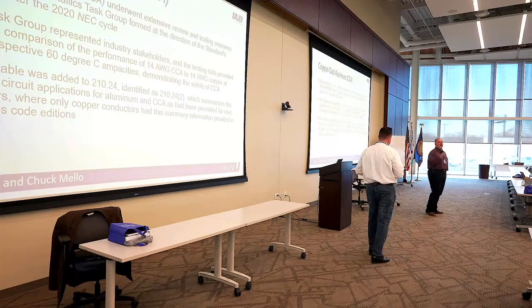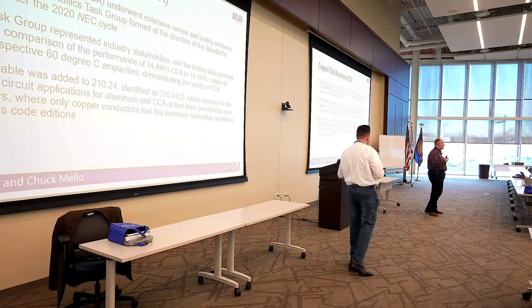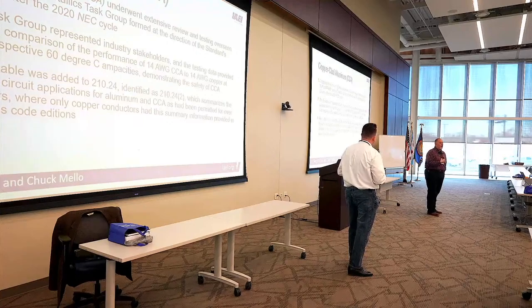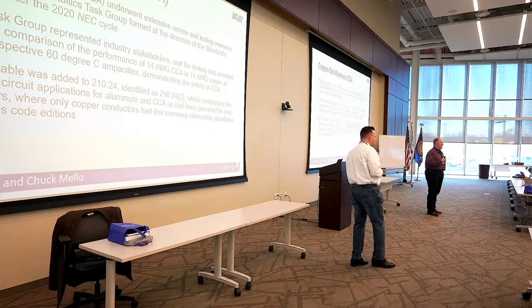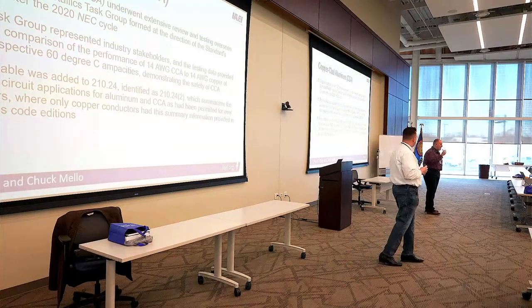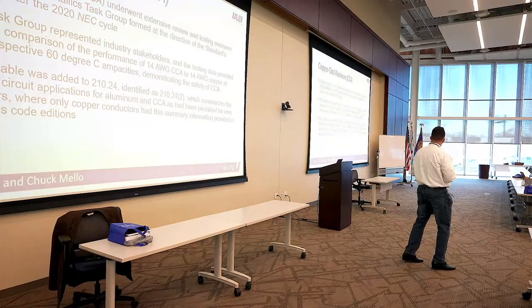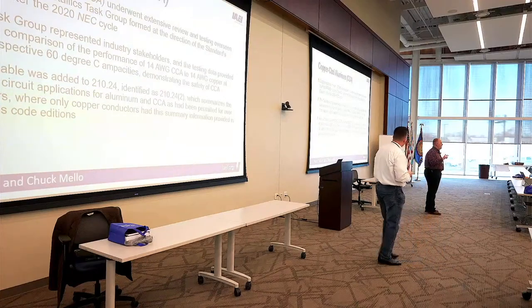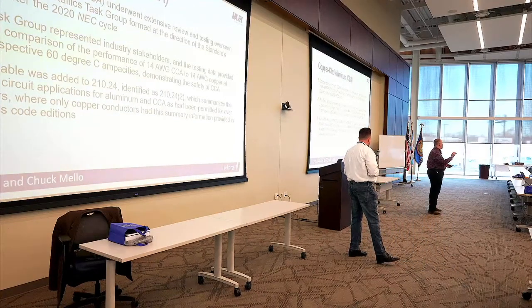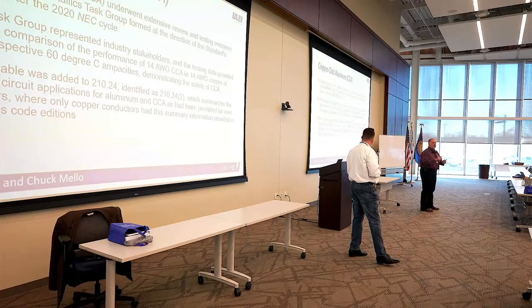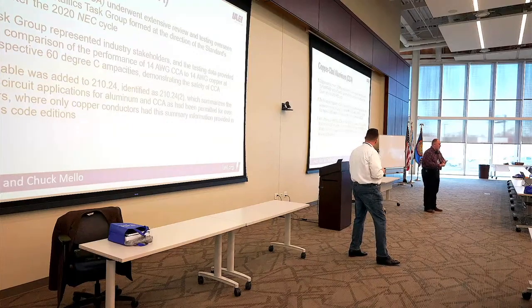So there were a bunch of public inputs in the 2023 code cycle. Panel two, we accepted the 10 amp circuit for AFCI in 210.12, and in 210.8 we recognized it. We also put it in the 2026, in the small conductor rule, I think. Yeah, we did. And then we recognize that we want to limit the use of a 10 amp circuit because we don't have a 10 amp receptacle, right?